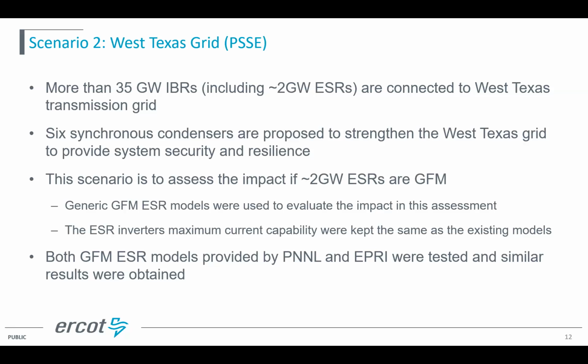The study basically tried to assess, if we convert the 2 gigawatt battery from grid following to grid forming, what is the impact? We use the models provided by PNNL and EPRI, and both models show pretty similar response. I also like to emphasize that when we switch the model, we respect the battery inverter maximum current capability. In other words, we only check the control change, without substantial hardware upgrade.